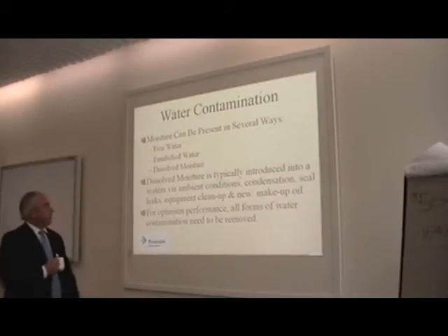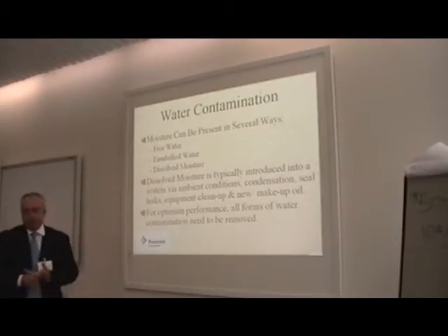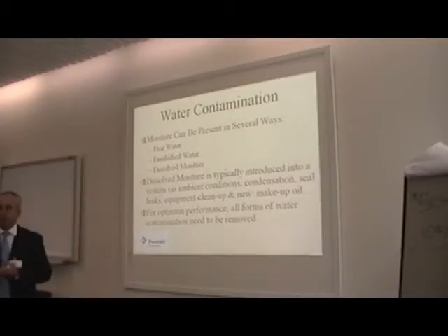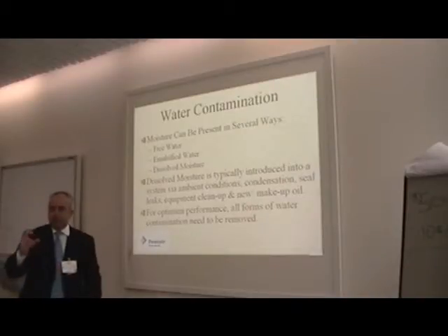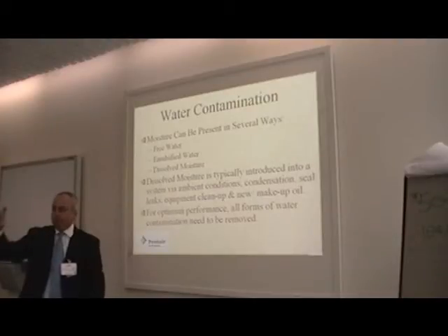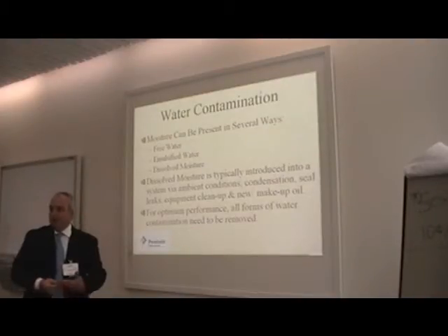Anyhow, when we talk about water as a contaminant, it exists, I would say, in 3 forms: free, emulsified, and dissolved. Free water is obvious. You take a sample, a bunch of water in there, it's free. Emulsified can be a chemical or a mechanical emulsion. Going through pumps at high velocities, you'll churn up really small water droplets, and they'll get very stable in the oil. That's the obvious one when you look at it. You should be able to read through an oil sample. If you can't read because the light blockage is there, then you've got a good emulsion. So that's your second phase.